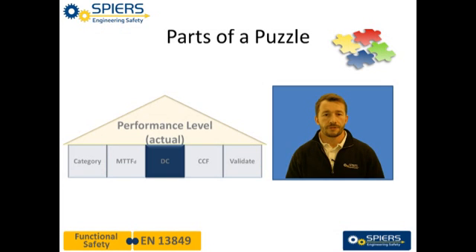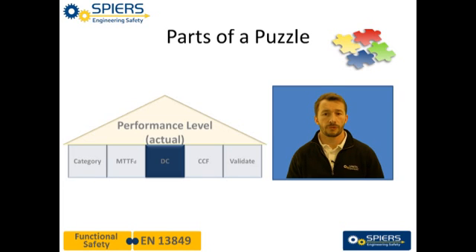Diagnostic coverage is the measure of the effectiveness of the diagnostics, which may be determined as the ratio between the failure rate of detected dangerous failures and the failure rate of total dangerous failures.